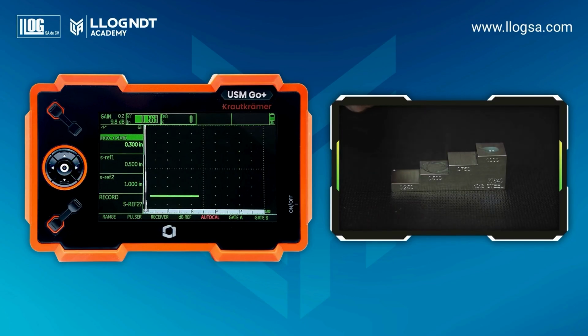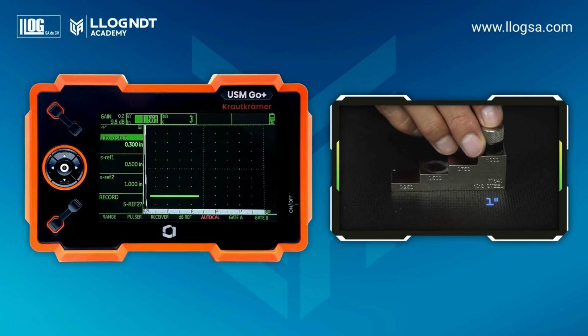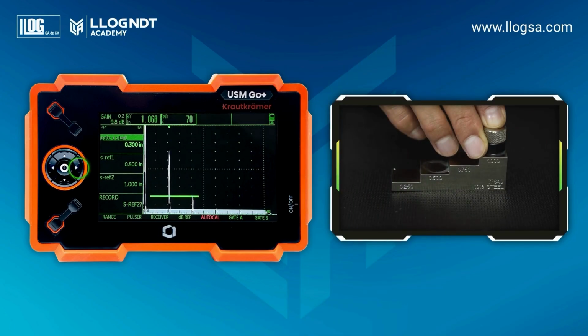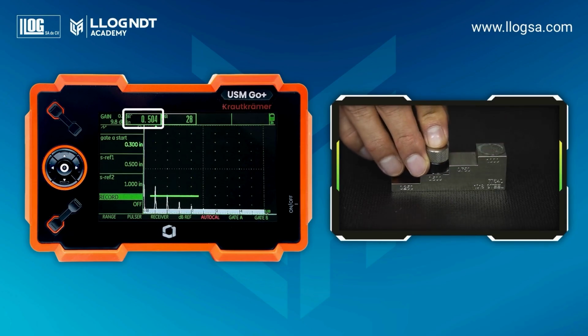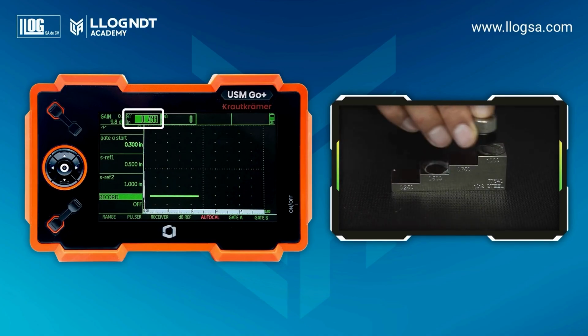Next, place the transducer on the 1 inch step. If necessary, adjust the gate so it aligns with the corresponding echo. To save the second reference, press the right key again in the record function. A message will appear at the bottom of the screen indicating that the calibration was successfully completed. Verify the reference values, 1/2 inch and 1 inch.